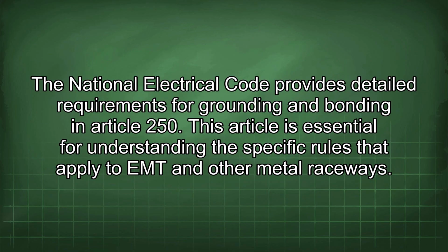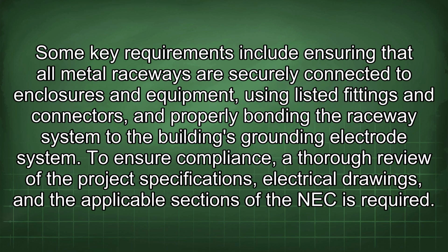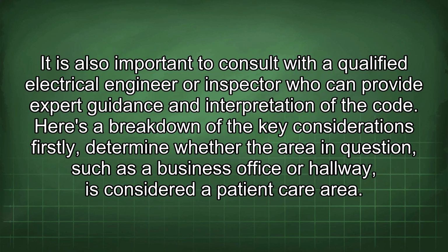The National Electrical Code provides detailed requirements for grounding and bonding in Article 250. This article is essential for understanding the specific rules that apply to EMT and other metal raceways. Some key requirements include ensuring that all metal raceways are securely connected to enclosures and equipment, using listed fittings and connectors, and properly bonding the raceway system to the building's grounding electrode system. To ensure compliance, a thorough review of the project specifications, electrical drawings, and the applicable sections of the NEC is required. It is also important to consult with a qualified electrical engineer or inspector who can provide expert guidance and interpretation of the code. Here's a breakdown of the key considerations.